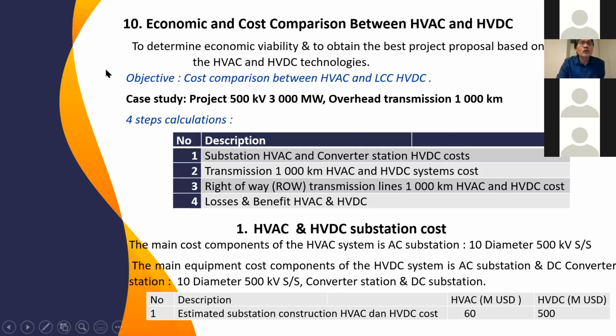So now we move to economic comparison. The objective here is cost comparison for a 500 kV, 3000 megawatt project for overhead line transmission for 1,000 kilometer. Because until now, there is no VSC with a rating of 3000 megawatt, 500 kV, we just make a cost comparison between HVAC and LCC HVDC. There are 4 calculation steps here. First, calculate substation cost. The second one, transmission cost. The third one, right-of-way cost. And the fourth one, losses or benefit.